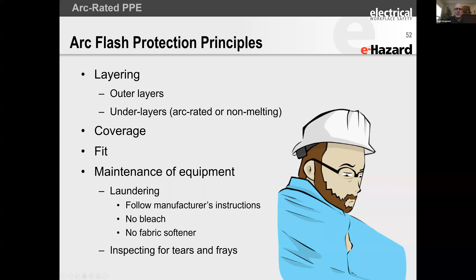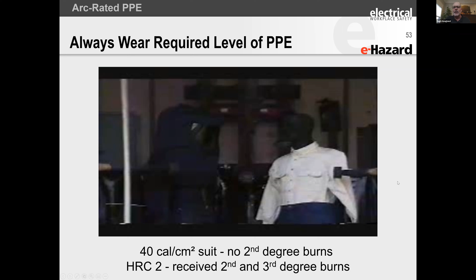This one obviously won't play, but I'll tell you what happens here. We hit a 40 cal suit, and we hit an 8 cal suit with a cotton t-shirt underneath, and we completely ignite the cotton t-shirt underneath. So going over the arc rating of a garment and wearing flammable material underneath really raises your risk. It's always better to either wear just the flame resistant arc rated garment, or put a flame resistant garment underneath if there's any chance of going over the energy you're predicting, or that the clothing will protect to - for legal protection and correctly identifying these things.